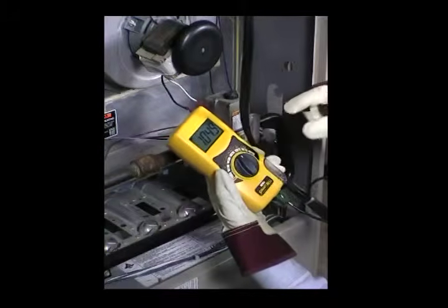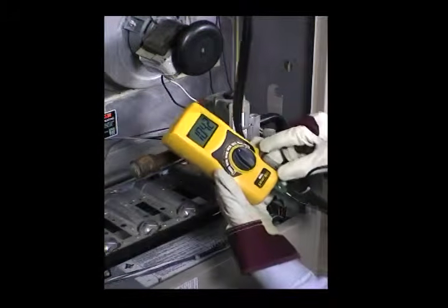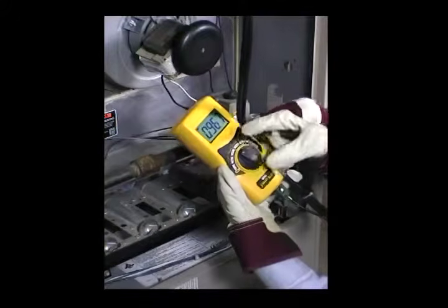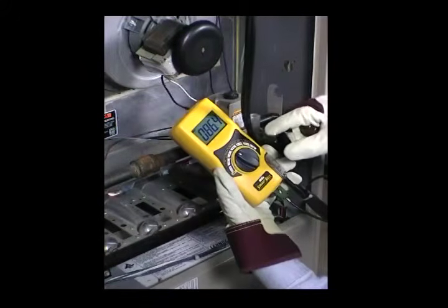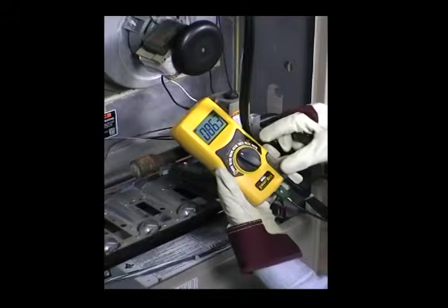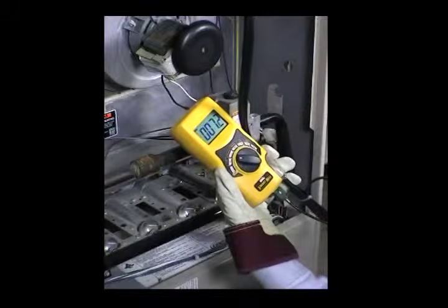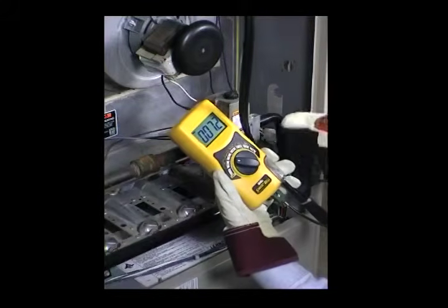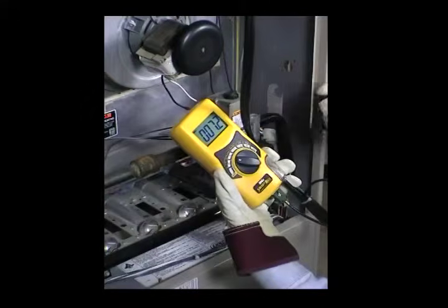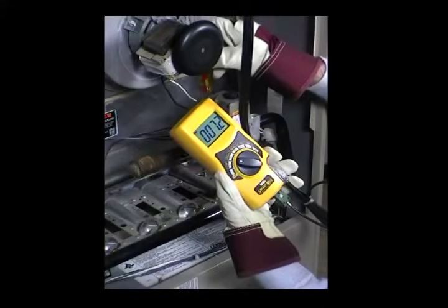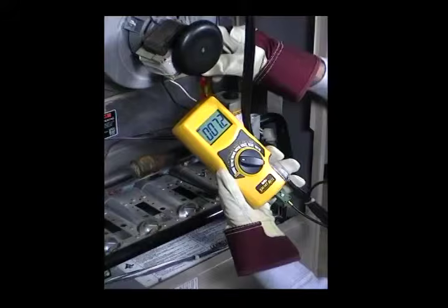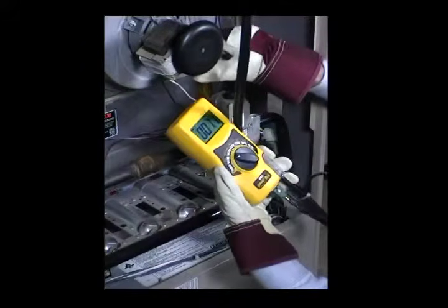Go to excess air to see what my calculated value for excess air is. I go back to the efficiency, and remember this is combustion efficiency. I can go to CO2. Now it's stabilized at approximately 7.2.